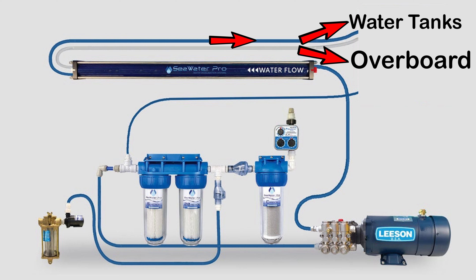The membrane splits the water into two things: one is the exhaust sea water which will be more salty than when it came in, and hopefully the other part will be fresh water. There's also a part that takes fresh water from our existing system and flushes this on a continual basis using a little timer. That'll make sure the membrane doesn't get filled with bacteria and other things when we're not using it — that's the fresh water flush.